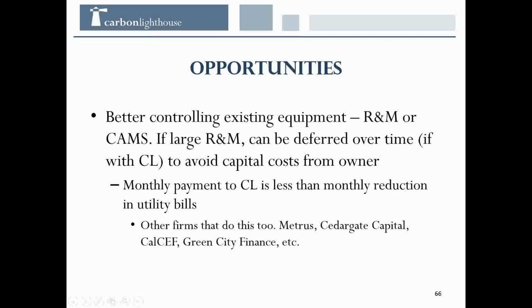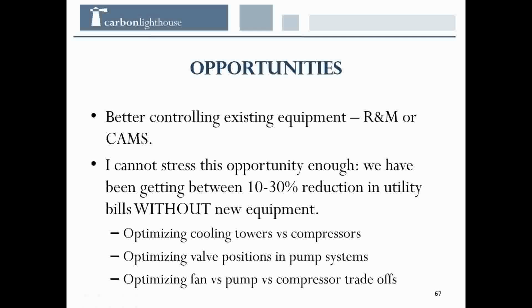That's made budgeting and other contract issues much easier. All right, we need another slide. Okay, so optimizing controls. This is key, and what you want to measure, using data loggers, is basically all the different current and power. Don't ignore power factor if you have large spinning machinery like chillers or other large motors. Power factor can change a lot based on load, especially if you have a VFD installed.